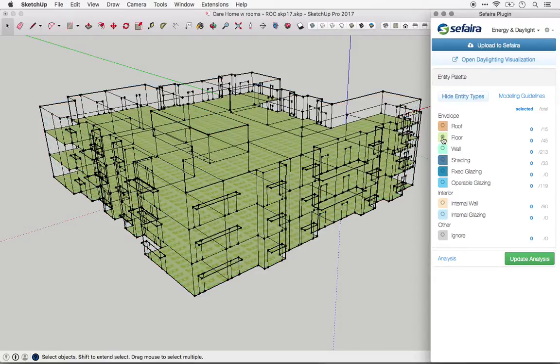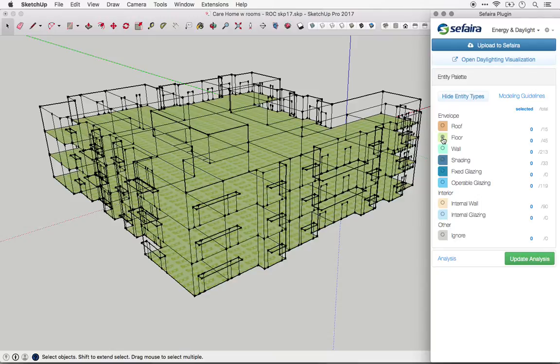Floor plates are used to calculate the total square footage of the building, and square footage is also used to calculate occupancy, lighting power, and equipment power of the building. So only occupied floor areas should be tagged as floor.